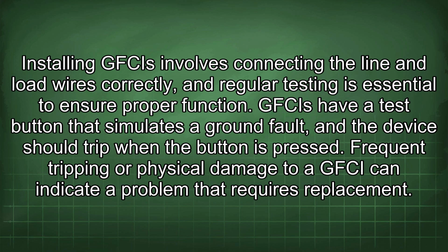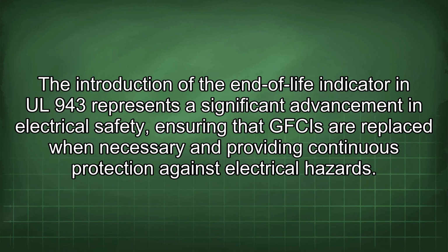Installing GFCIs involves connecting the line and load wires correctly, and regular testing is essential to ensure proper function. GFCIs have a test button that simulates a ground fault, and the device should trip when the button is pressed. Frequent tripping or physical damage to a GFCI can indicate a problem that requires replacement. The introduction of the end-of-life indicator in UL 943 represents a significant advancement in electrical safety, ensuring that GFCIs are replaced when necessary and providing continuous protection against electrical hazards.